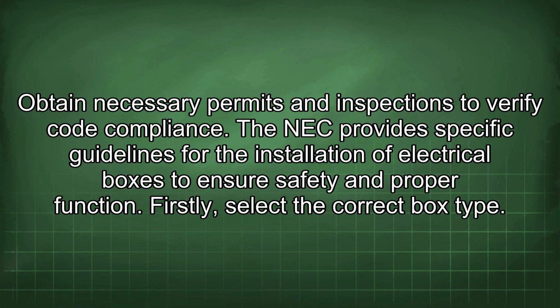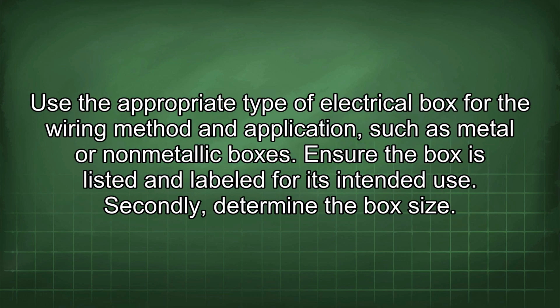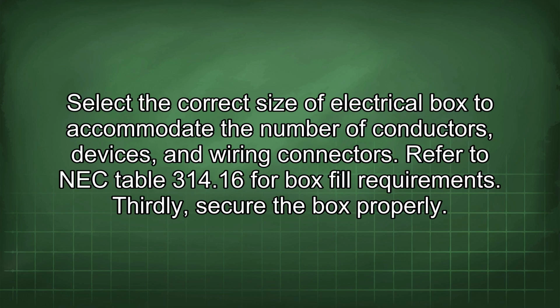Firstly, select the correct box type. Use the appropriate type of electrical box for the wiring method and application, such as metal or non-metallic boxes. Ensure the box is listed and labeled for its intended use. Secondly, determine the box size. Select the correct size of electrical box to accommodate the number of conductors, devices, and wiring connectors. Refer to NEC Table 314.16 for box fill requirements.